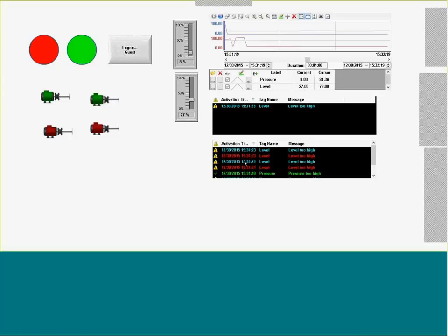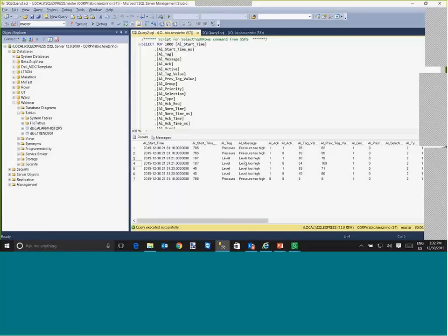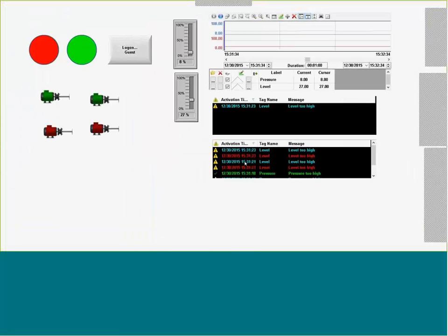It's much easier for an external system to understand and retrieve data from a SQL relational database table, which supports the standard SQL commands, than retrieving data from the InduSoft proprietary files, binary files, which are, again, by definition, proprietary. It would not be so easy for an external system to retrieve data from InduSoft history file, trend or alarm, and manipulate this data. So whenever you want to share this information with other systems, an external database is a better option.